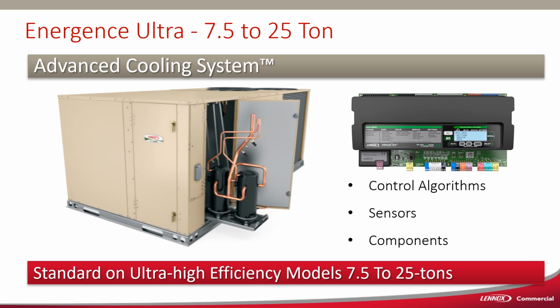And the 7.5 all the way up to the 25 ton utilizes the tandem compressors. You see this would be a B box, 7.5 through 12.5 ton, and you have 2 tandem compressors. Those compressors are mounted on that sliding tray that slides out of the unit. That is one part. If you lose one of those compressors and you order a new compressor, you're going to get both compressors. They're already going to be mounted on that slide out tray. They're already going to be piped together, and those pressure switches and sensors and the Schrader valves that are on there are already going to be in there. If this had been a larger unit, like a 25 ton or a 20 ton, then you would have 2 of these slide out trays, 2 tandem compressors on each tray.